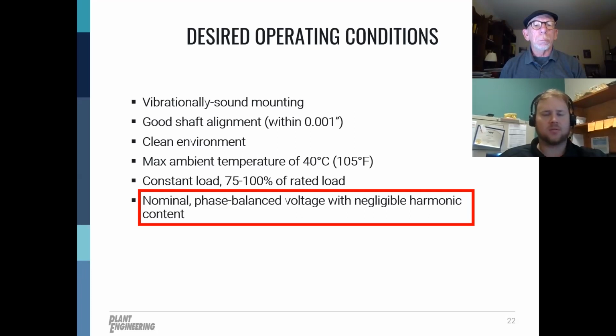And then finally, the last operating parameter we talk about is rated load. The motors are designed to be operated at their rated load. So if you ran a 10 horsepower motor at 5 horsepower, the efficiency is going to be poor, and also the power factor will be very low. Both of these things, efficiency and power factor, cost you on energy bills. So a common problem across the industry is the opposite of what I just said, or actually it's the same: oversizing the motor.